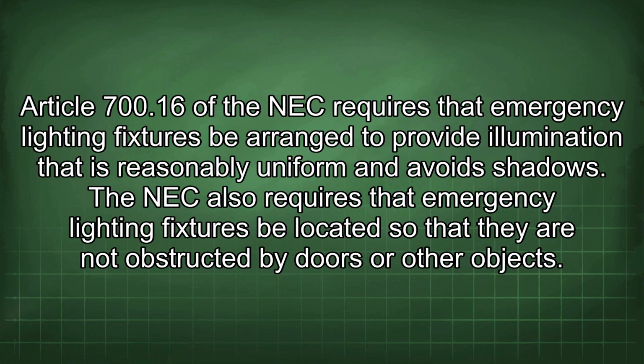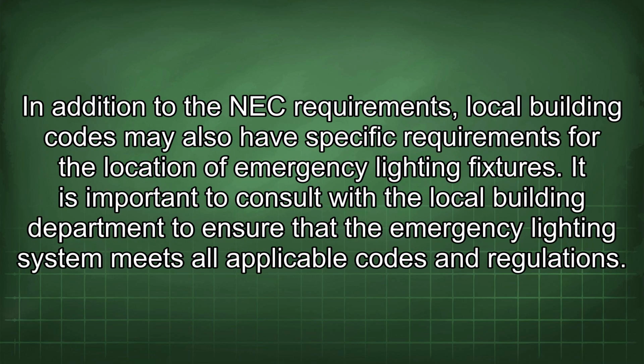Article 700.16 of the NEC requires that emergency lighting fixtures be arranged to provide illumination that is reasonably uniform and avoid shadows. The NEC also requires that emergency lighting fixtures be located so that they are not obstructed by doors or other objects. In addition to the NEC requirements, local building codes may also have specific requirements for the location of emergency lighting fixtures. It is important to consult with the local building department to ensure that the emergency lighting system meets all applicable codes and regulations.